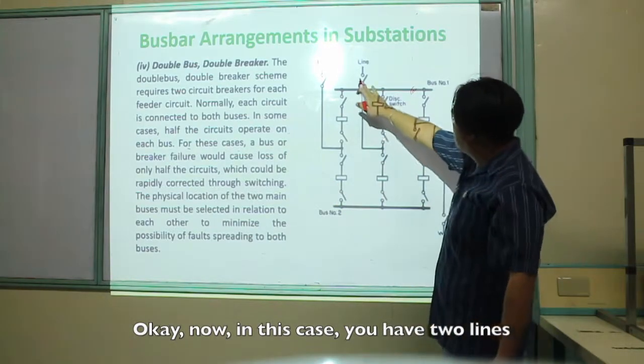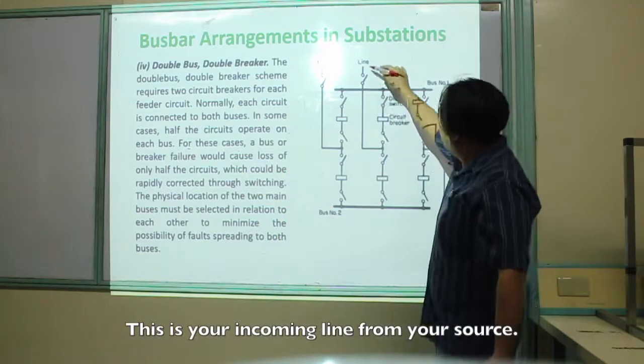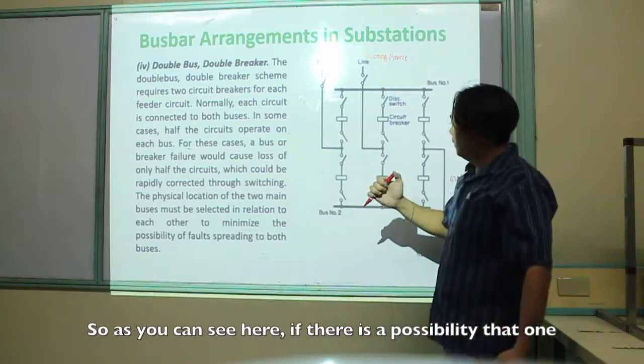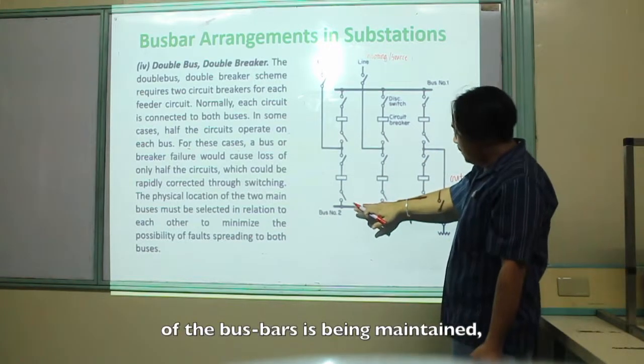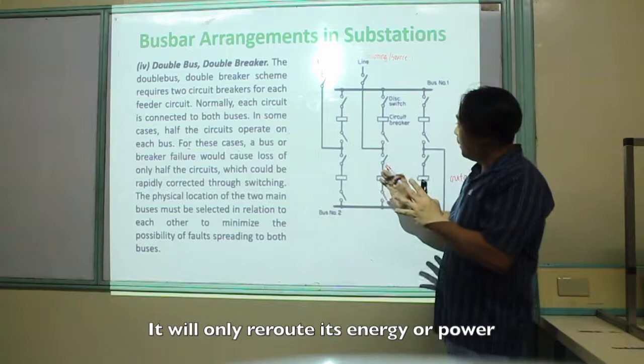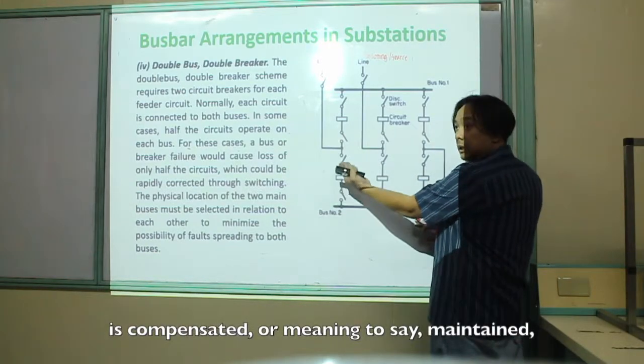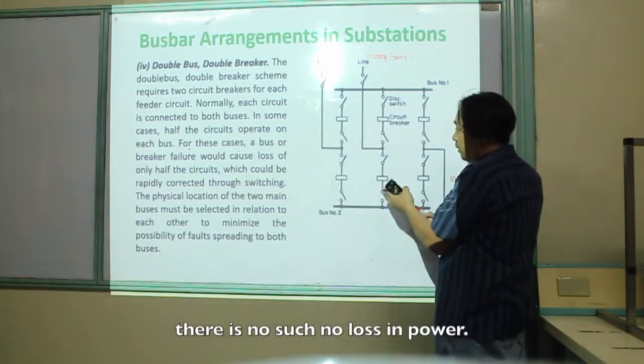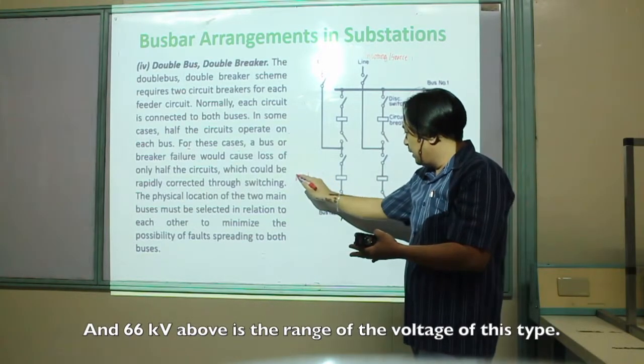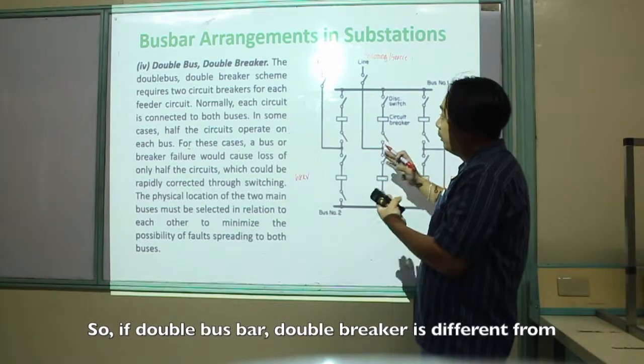In this arrangement, you have two lines and your outgoing line and your incoming line from your source. If there is a possibility that one of the bus bars is being maintained, the power is not cut off — it will only reroute its power to bus number one. Even if one of the breakers is maintained, there is no loss in power. This type is N-2 and operates at 66 kV and above.